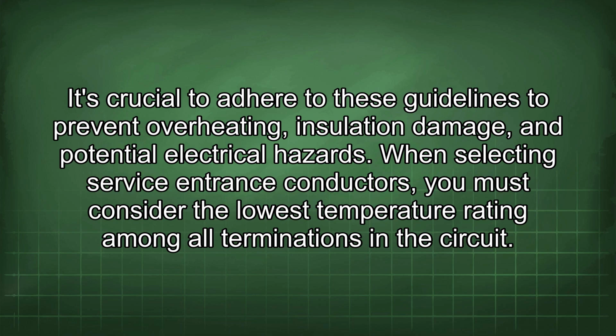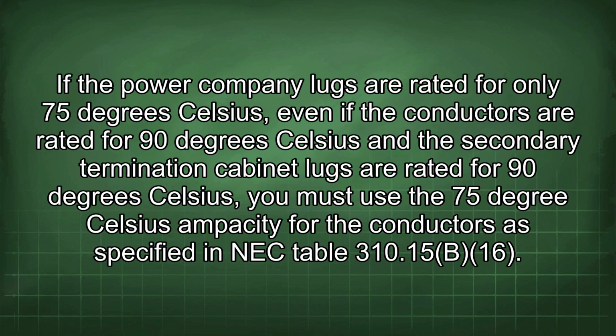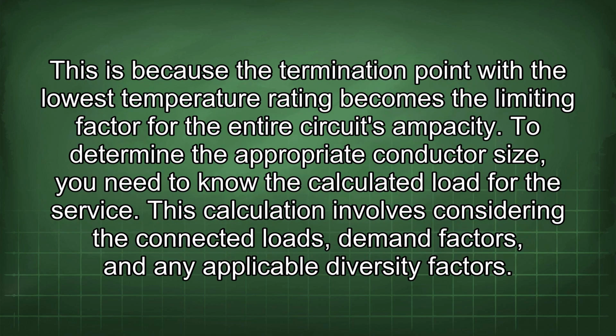When selecting service entrance conductors, you must consider the lowest temperature rating among all terminations in the circuit. If the power company lugs are rated for only 75°C, even if the conductors are rated for 90°C and the secondary termination cabinet lugs are rated for 90°C, you must use the 75°C ampacity for the conductors as specified in NEC Table 310.15(B)(16). This is because the termination point with the lowest temperature rating becomes the limiting factor for the entire circuit's ampacity.